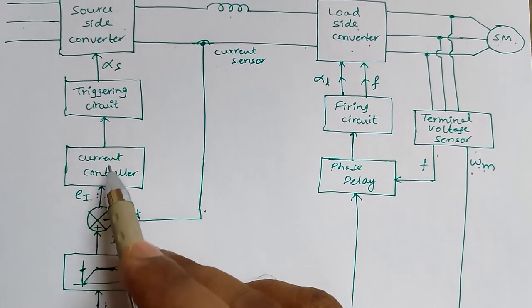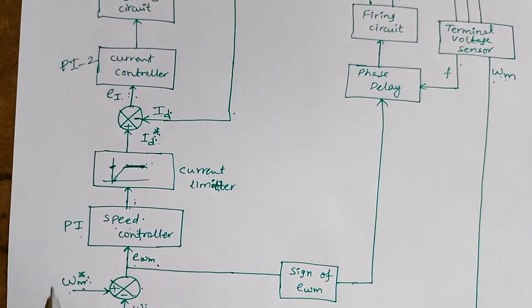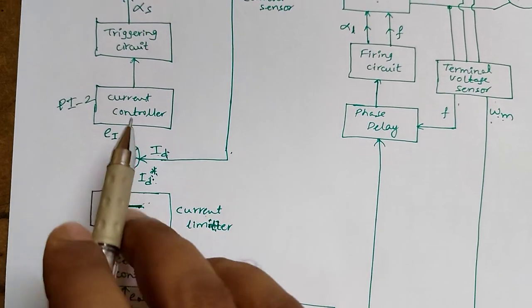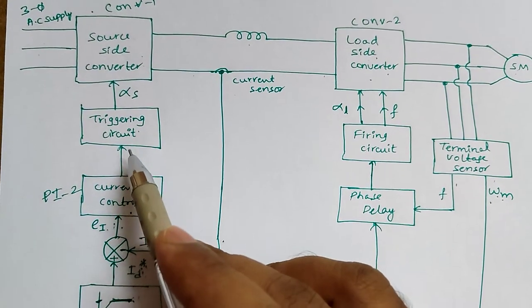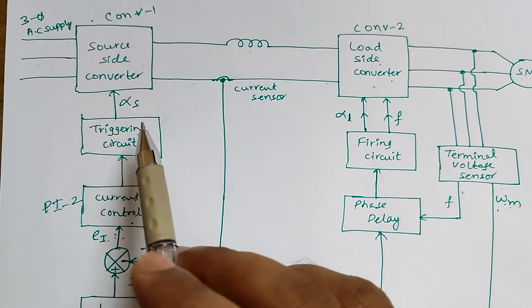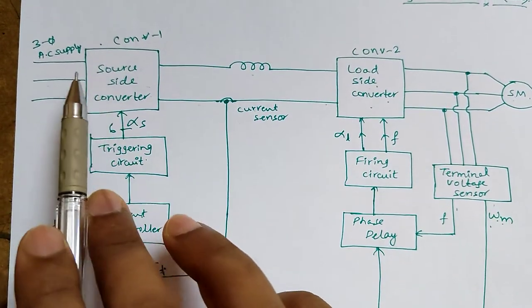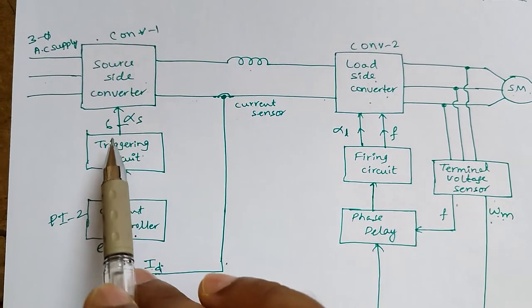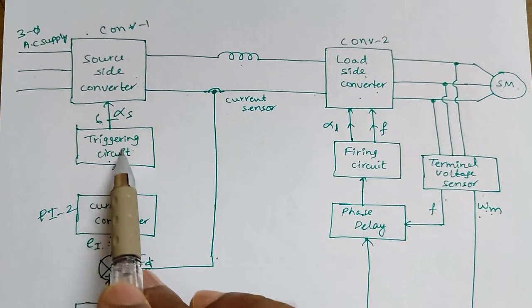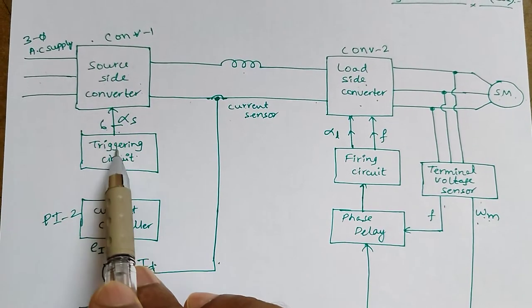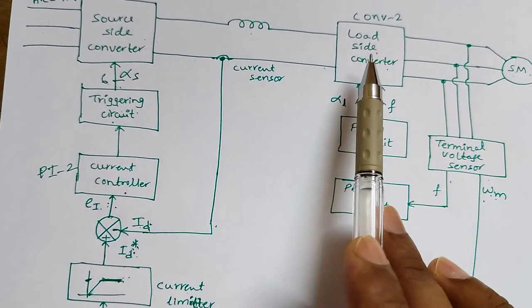The current error is connected to the current controller, which is a second PI controller (PI2), while the first PI controller (PI1) is the speed controller. The output of the current controller is given to the triggering circuit, which generates six firing pulses. These six firing pulses are connected to the source side converter — a three-phase rectifier with six controlled switches — and the triggering circuit generates these six firing pulses with 60-degree displacement. This completes the closed loop path.